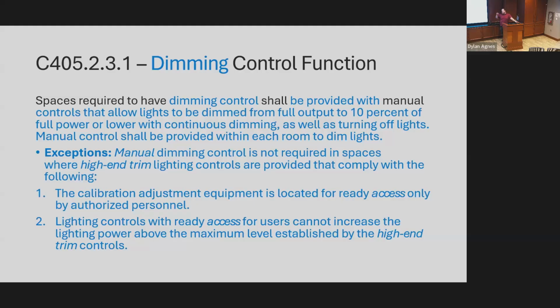Step dimming digitally is fantastic. Step dimming analog, very cumbersome. But the digital version of that control strategy, I think, is very well done. But as far as dimming, I would do high-end trim if you don't want to deal with dimming and you want to have your basic light switch for scenes 0, 1, 2, 3, 4, 5.